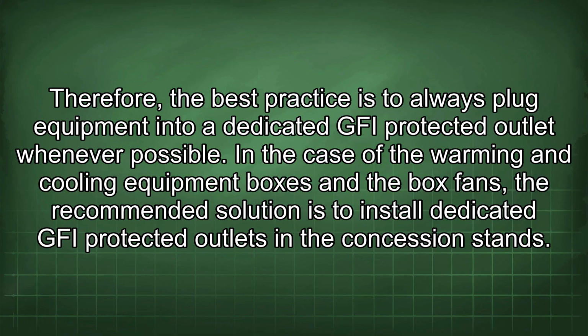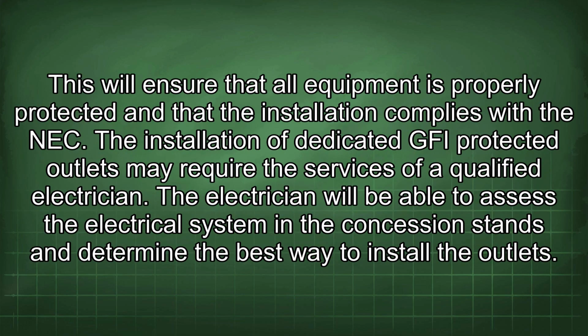Therefore, the best practice is to always plug equipment into a dedicated GFI protected outlet whenever possible. In the case of the warming and cooling equipment boxes and the box fans, the recommended solution is to install dedicated GFI protected outlets in the concession stands. This will ensure that all equipment is properly protected and that the installation complies with the NEC.